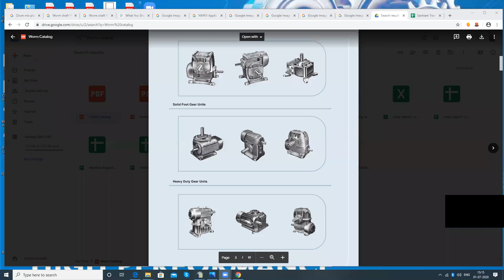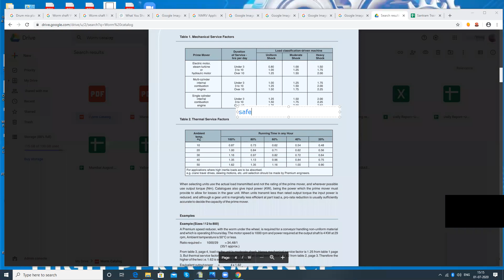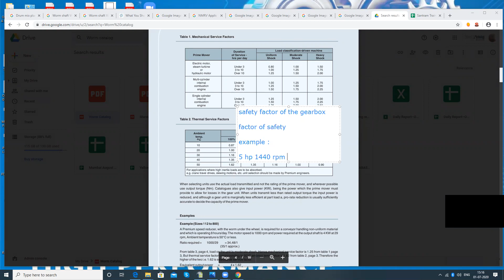Now the other thing we can discuss is on the next page. That is the important part. That is the safety factor. So let me now introduce one of the most important terms in the selection of a gearbox. That is known as the safety factor of the gearbox, also known as factor of safety. Okay. So what is that? Basically, let me give you a very good example. There is a 5 HP 1440 RPM foot mounted motor, and you have to get 100 RPM output speed.